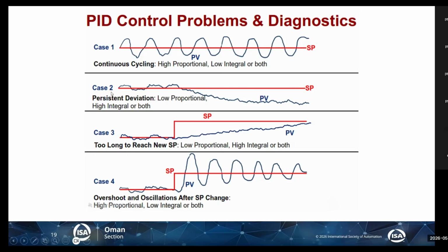I have case 2, persistent deviation. It keeps on dropping, going away from the set point. It's not able to reach the set point. And this is typically because of low proportional or high integral or both. If I have a very low proportional, the controller is very weak. It's not aggressive, so it cannot reach the desired set point.